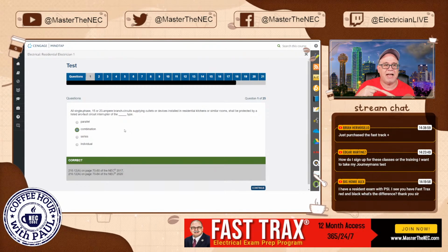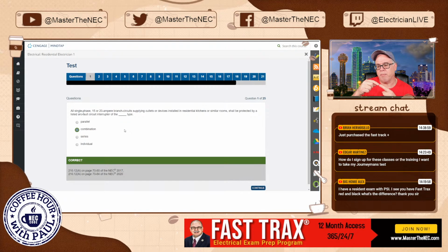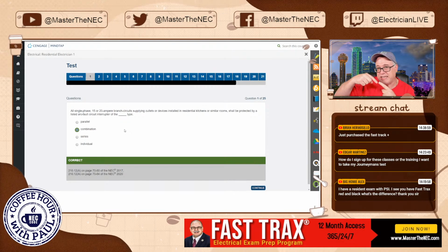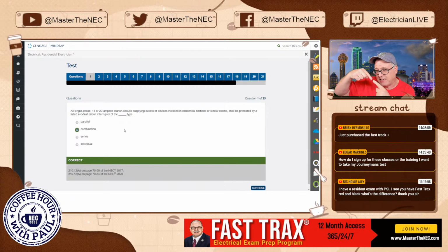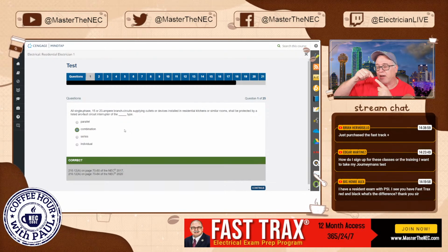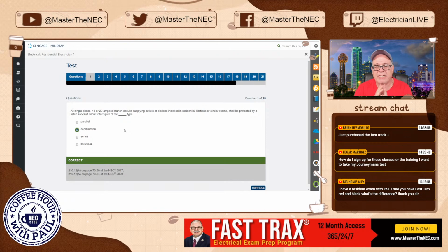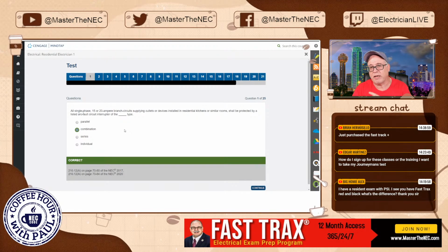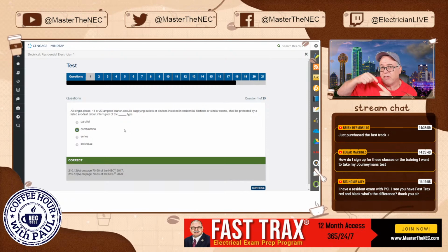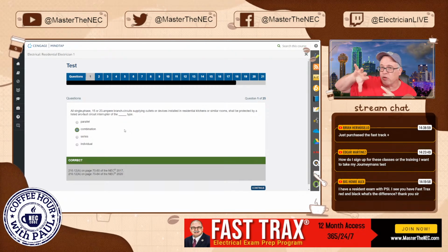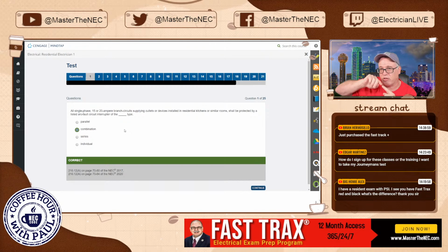Another example is a wire that's been damaged and frayed and is barely touching, like a black wire that's crushed, then it arcs over that. Now, the key difference between a parallel and series arc when it comes to the load is that a series arc is very load dependent. In other words, if there's no load being drawn, then that arc is not going to generate.